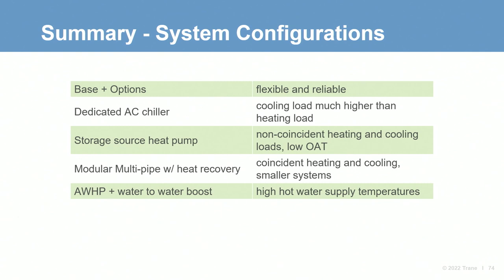So, to summarize the chiller heater system configurations we discussed, the dual feed decoupled four-pipe distribution system is quite flexible and reliable. However, some applications may be better served by an alternate configuration. Reasons for selecting one of the alternate configurations are shown, but note that the higher order systems will require more complicated controls, and system costs are likely to increase as well.